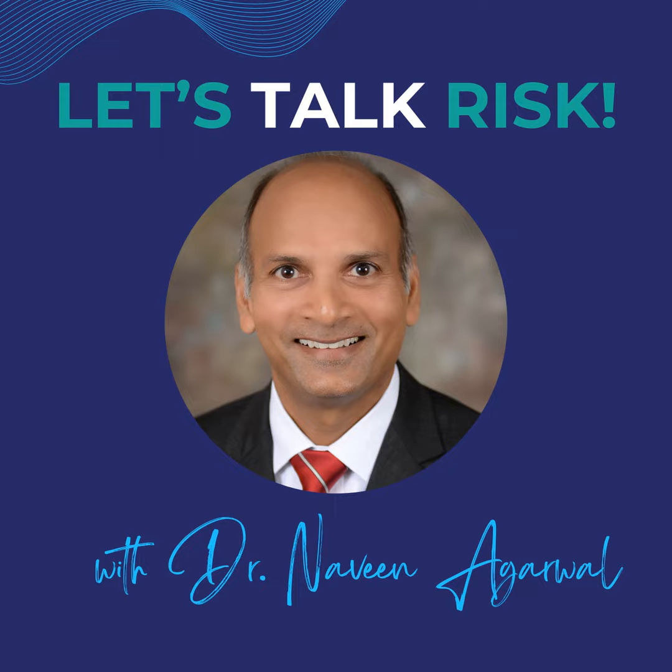Yeah, I mean that's a good question, Robbie, because it is the hardest stuff. It goes back a little bit to the discussion last week with Mark, where from that point you really need to sit down and, I mean, you don't necessarily have to have a clinician or whoever's going to be a user on the project team, but you have to have discussions with them, early on when you're doing your rapid prototyping, to get that immediate feedback and understand how the product would be used, which is really setting up your framework to look at the risks for it. There's always trying to look at predicates and looking at similar products, but if you're really making something new, that's why startups are very hard and can be a bit challenging.